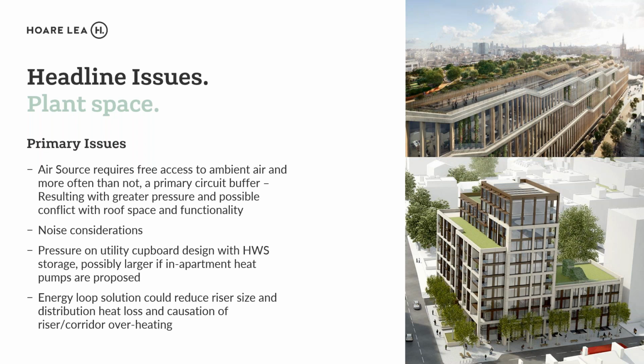There's also, depending on the design of hot water, whether you include hot water storage in your distribution when heat pumps are used, looking at the utility cupboard inside the apartments, that may need to grow to include hot water storage. And we're finding that there's a lot of discussion about energy loop solutions, where you provide a sort of ambient loop throughout the building and look at the heat pump generation, but placing it in the apartments. And I'll come on to the pros and cons of that a bit later, but using that energy loop will actually aid the heat gain that the corridors and risers see currently on elevated temperatures, where overheating in many places occurs.